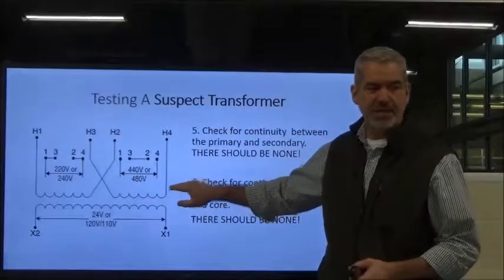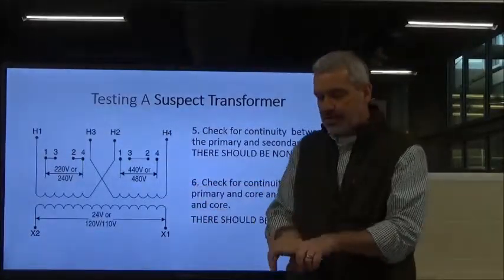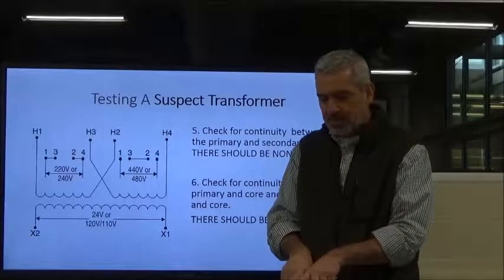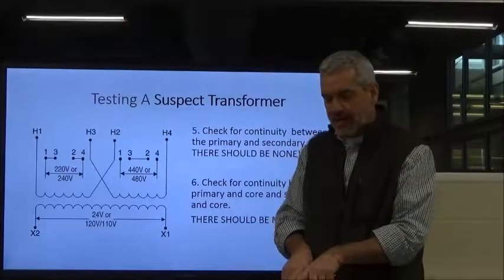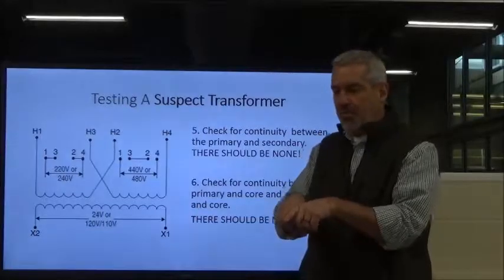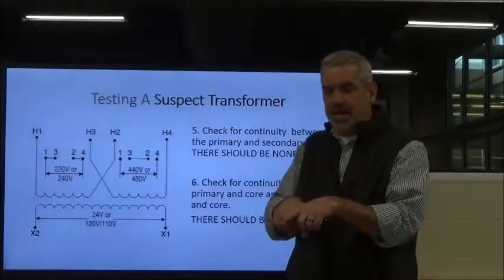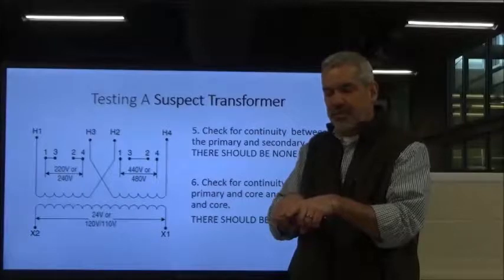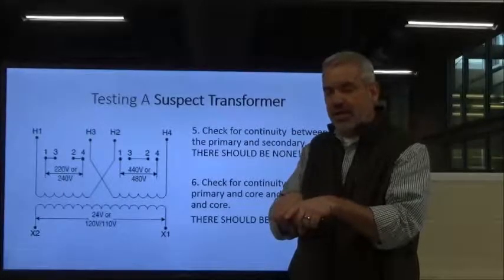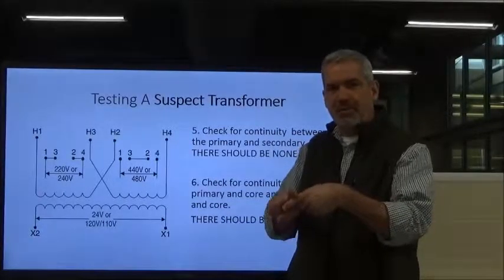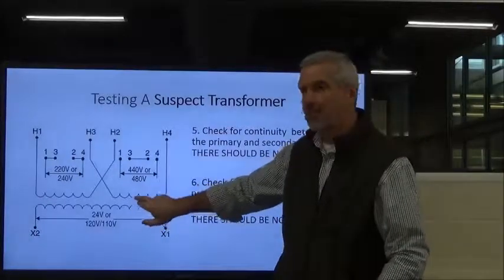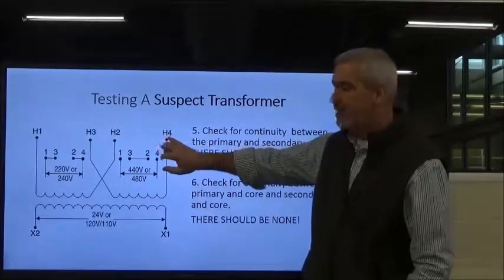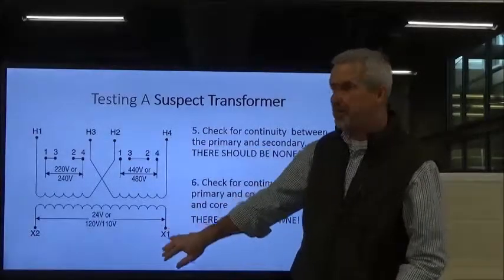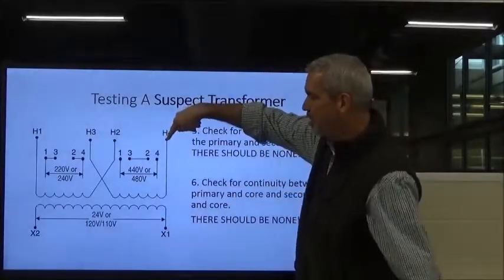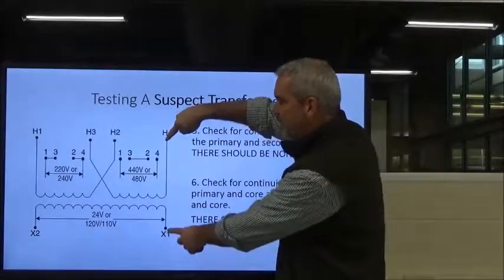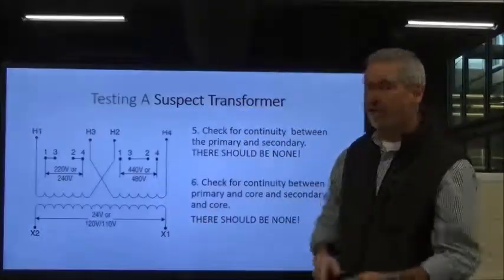That's something we don't want to happen, because they are separated, a lot of times with a paper insulation. If that insulation were to degrade to the point where it no longer separates the two, again because of the vibration and the heat in there, the insulation can abrade between the primary and the secondary. You could have a short between these two. You do not want any type of continuity between your primary and your secondary. So take your meter, put it on one end of your primary and check it to your secondary. You should not have anything at all, okay?